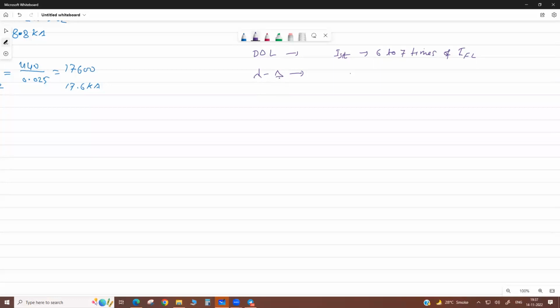Now in automatic it is done by a time delay relay. But here there is a disadvantage. During this transition period, motor does not get a voltage, and there is a sudden change. Your voltage is multiplied by √3 times. Then there is a jerk on the motor shaft. Okay, stresses will be developed. That's why we avoid this also. Then next is the primary rotor resistance starter. Rotor resistance starter is for slip ring motors only.